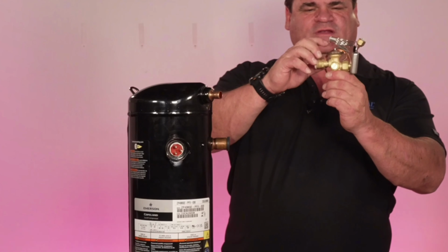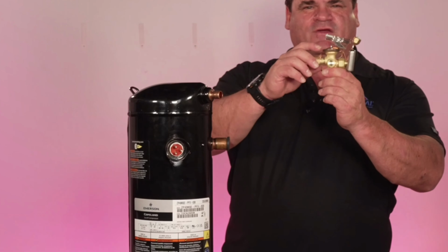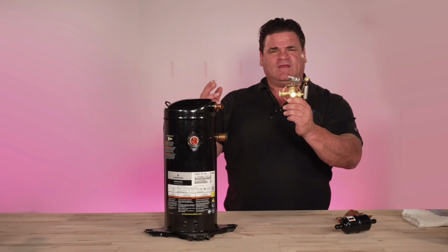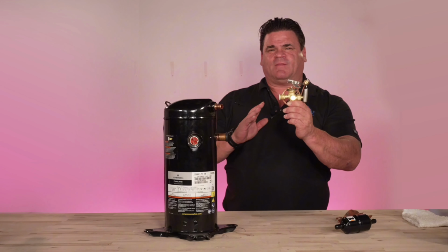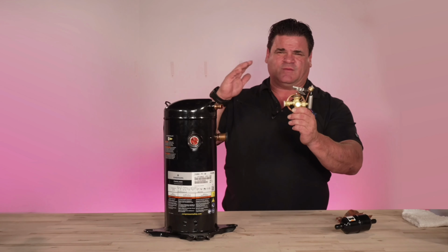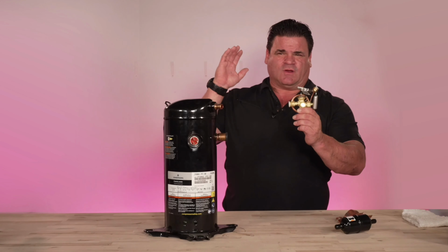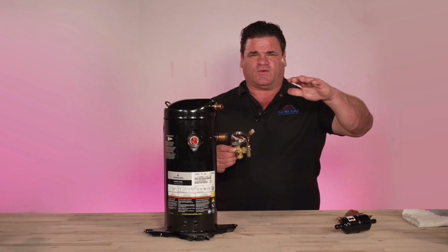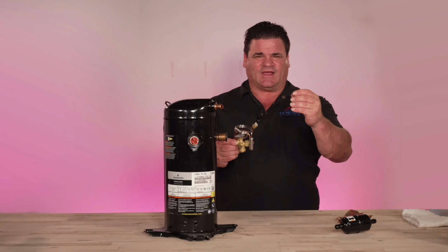And it's gonna go to the top of this TXV. And you're gonna have refrigerant coming in and out of this TXV. When it enters, it's going to be metered, meaning based on the demand is going to determine how much the demand for cooling. So if it's high demand, it's a hot house, hot building, it's going to push a lot of refrigerant into the evaporator coil. All right. As that demand decreases, it will start to close and less will flow in.